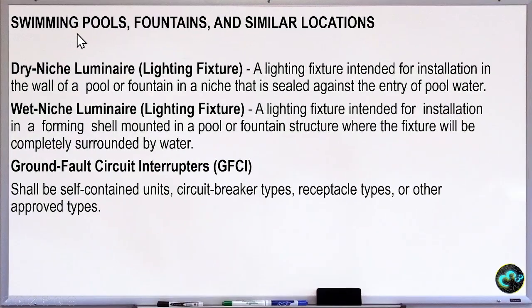Okay. Then swimming pools, fountains, and similar locations. So we have the dry niche luminaire, a lighting fixture intended for installation in the wall. So ito sa wall ng ating pool or fountain, in a niche that is sealed against the entry of pool water. So this is waterproof, so talagang walang papasok na tubig. Wet-niche luminaire, a lighting fixture intended for installation in a forming shell located in a pool or fountain structure where the fixture will be completely surrounded by water.